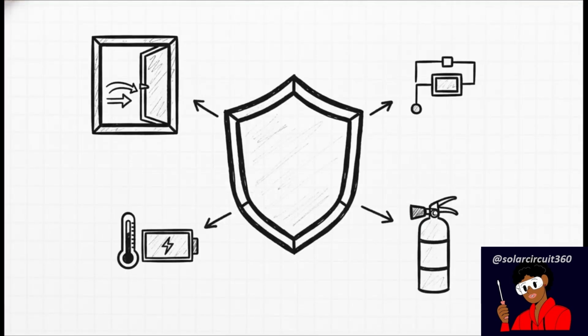And that is safety. Seriously, this part is completely non-negotiable. When you load test a battery, you are dealing with a huge amount of energy. So you need a well-ventilated area, you absolutely have to use a fuse on the positive wire, that's your protection against a dead short. Use insulated tools, keep a close eye on the battery's temperature, and for goodness sake, have a fire extinguisher handy. You have to respect the power you're working with.